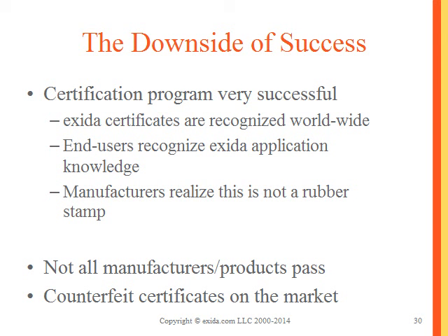We, for example, will not issue a certificate where, and you can look in our blog history, a couple of blogs that I posted, may have been a year ago already, an assessment, apparently another company's assessment, showed that there were safe failure rates for a ball valve that was not connected to anything. I don't see how that valve can transition to the safe state without something being connected to it, so that simply doesn't make sense.